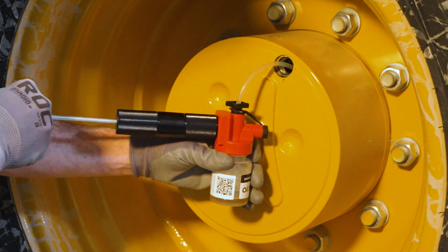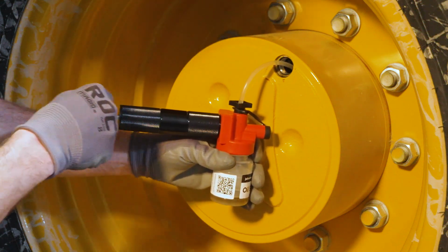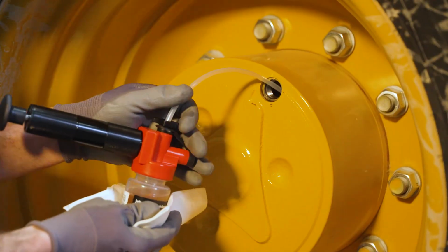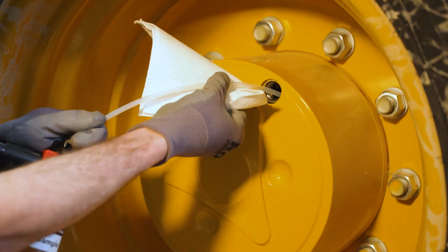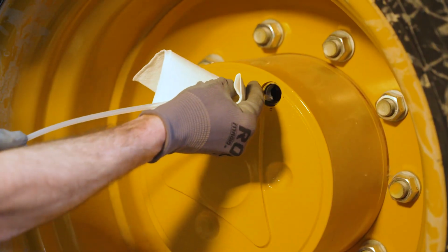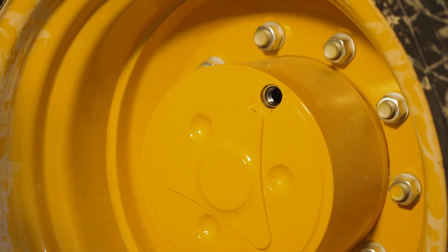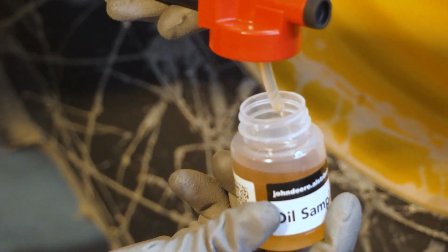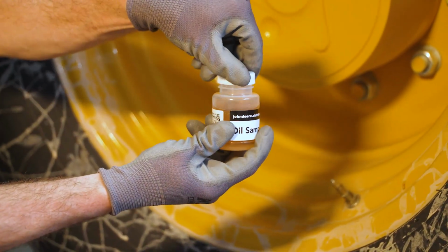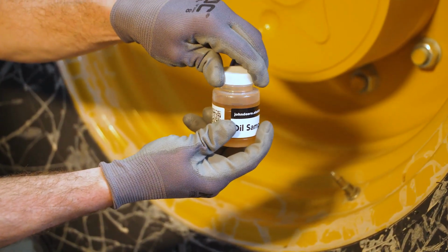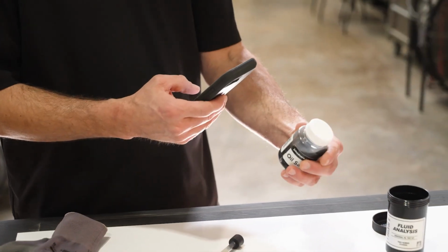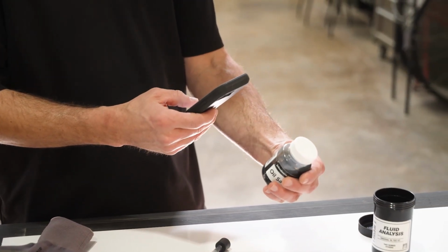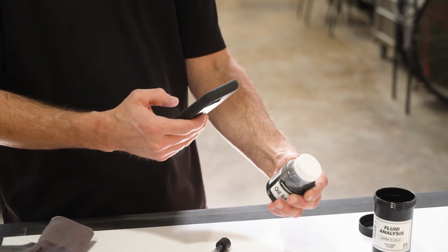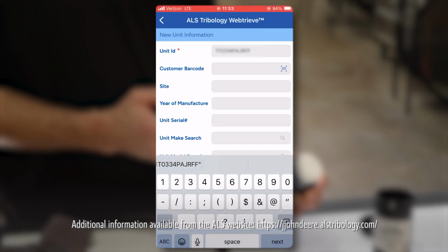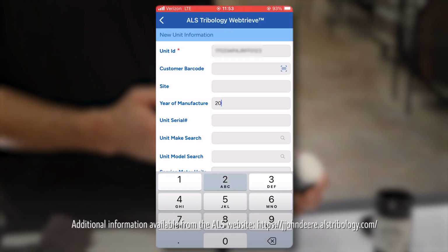Fill the oil sample bottle approximately 80 to 90% full. Once the sample bottle has been filled to the appropriate height, which will be marked on the sample bottle, the bottle can be removed from the pump and the lid placed back on the bottle. Use the same procedures as you would if you obtained a sample using the polycap probe. Scan the QR code on the bottle and complete all equipment and sample information electronically using the Webtrieve app.